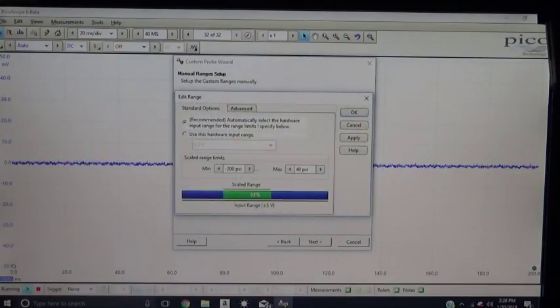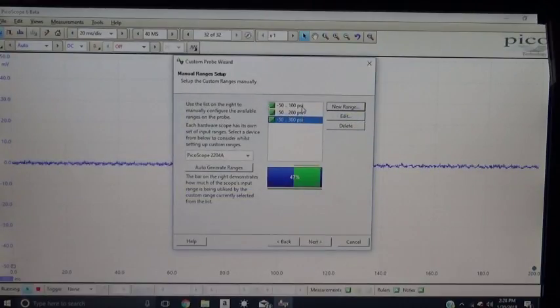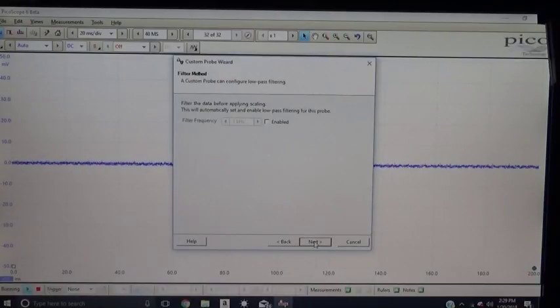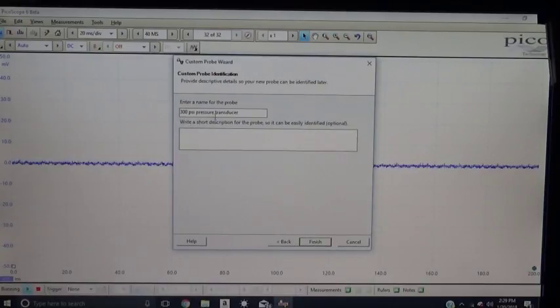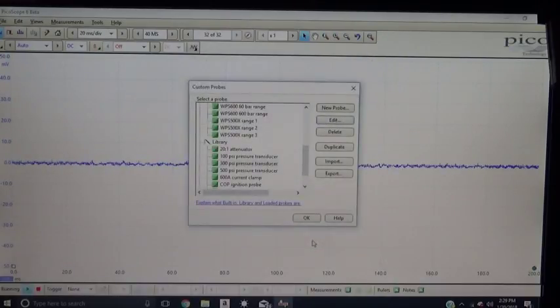New range, 50 psi to 200 psi. Okay, new range, again you can do whatever you want to do here, it's up to you guys, whatever you want to customize. That's a 300. Okay, so now I can choose up to 100 psi, 200 psi, or 300 psi on my scale. So click next, you're done. Next again, 300 psi pressure transducer, and you click finish, you're done with that one.